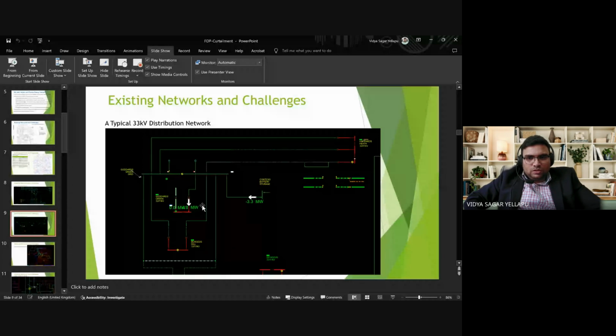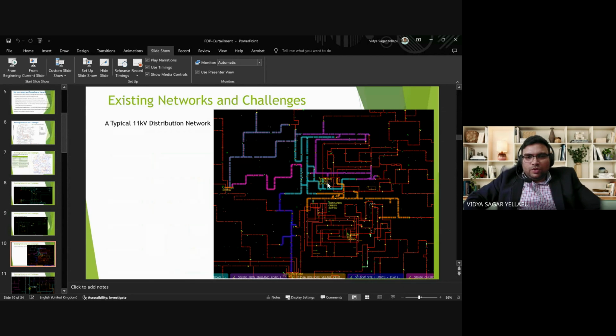If we go a bit further, this is the 33 kV substation. We can see the bus bars here, and these are the transformers or grid transformers. They step down from 132 kV to 33 kV, and these are transformers associated with the various primaries. This is one of the primaries. We have three transformers here, which are 33 kV by 11 kV transformers. And if we go further, this is the network of that particular primary.